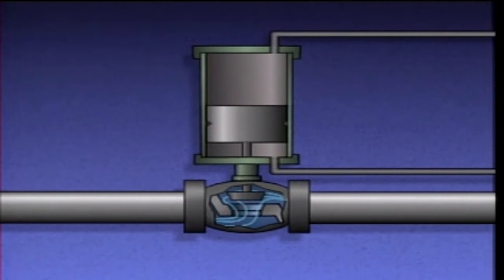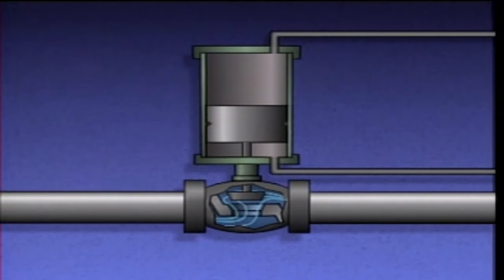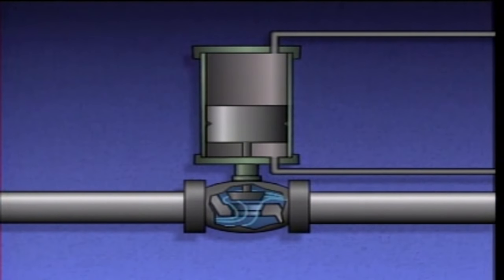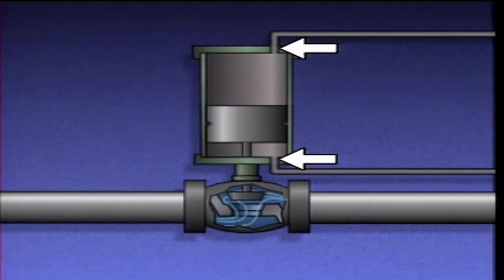There are also piston actuators that have air pressure supplied to both sides of the piston. This type is called double-acting. The parts of a double-acting piston actuator are similar to the single-acting type, but it does not have a spring, and there is an air supply port on each end of the cylinder.